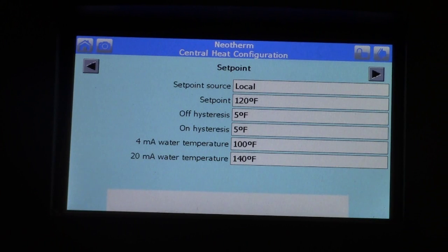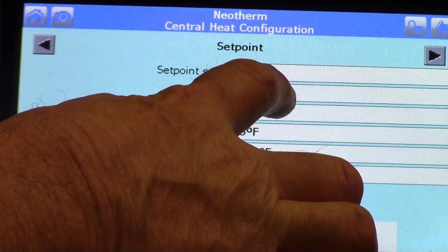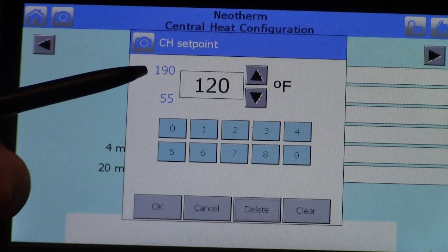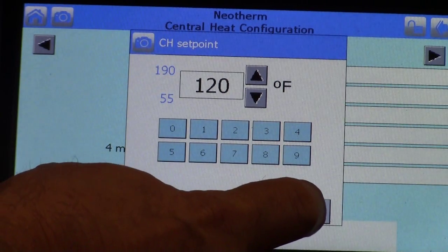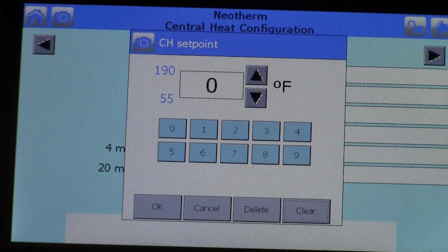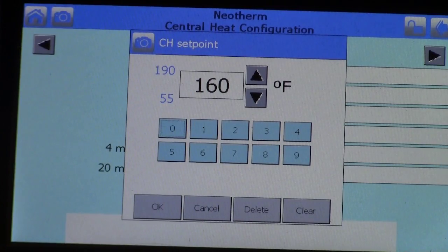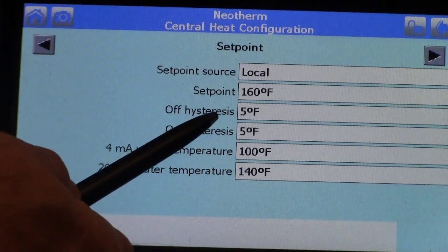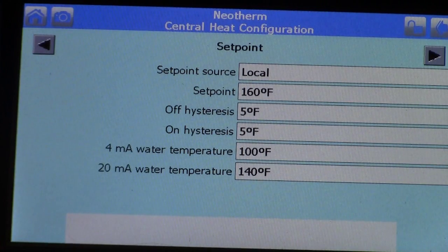Set points are all defaulted coming out of the factory at 120 degrees, since we don't know the application it's going into. Hypothetically, let's say you need a 160-degree central heat set point on the coldest day of the year. Click on the 120 and that brings up another screen. On the right-hand side you'll see it reads 55 to 190 — that's the range in which you can set your set point. Press clear and plug in 160 for a fan coil application needing roughly 160 degrees. Press OK and that brings us back to the set point screen now showing 160. The differential is a 5-degree off differential, so the off point becomes 165, and the on differential is 5 degrees, making the on point 155.